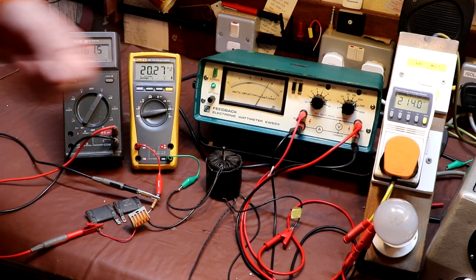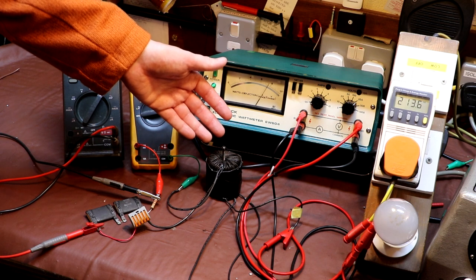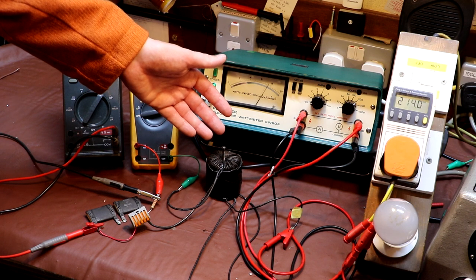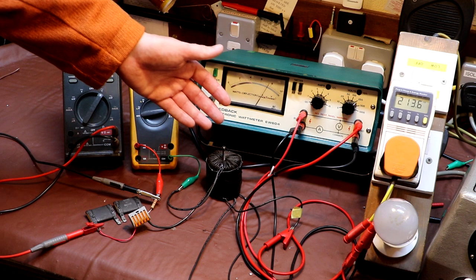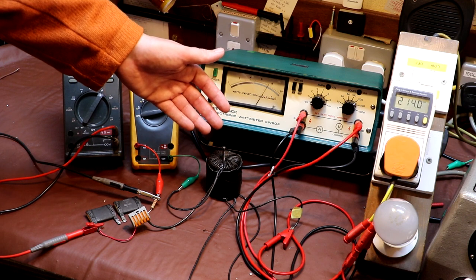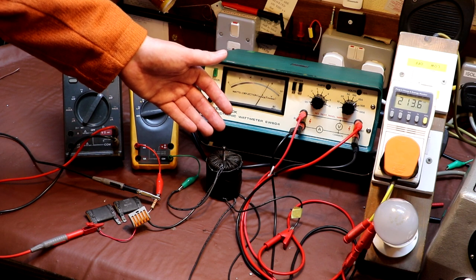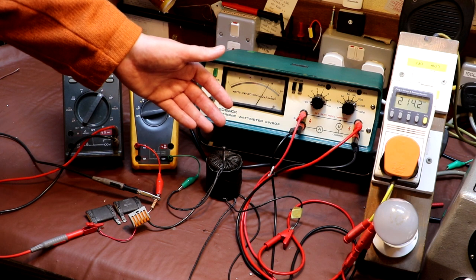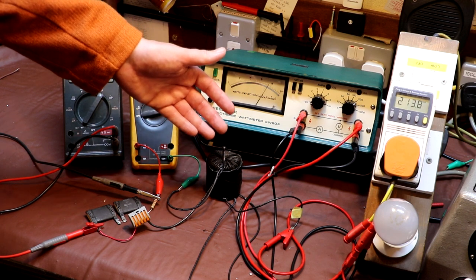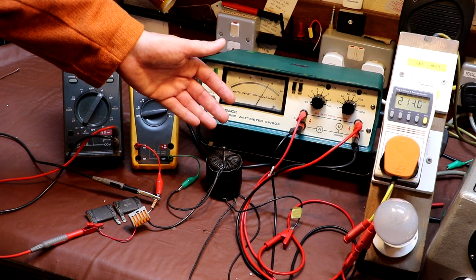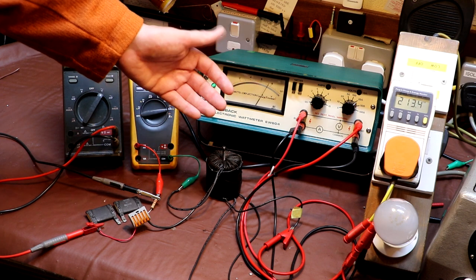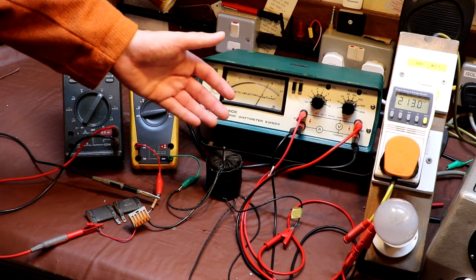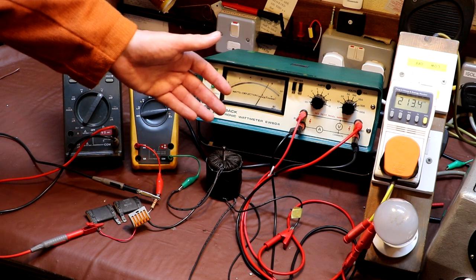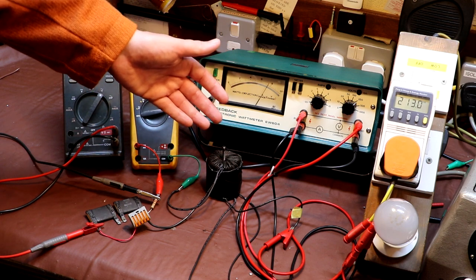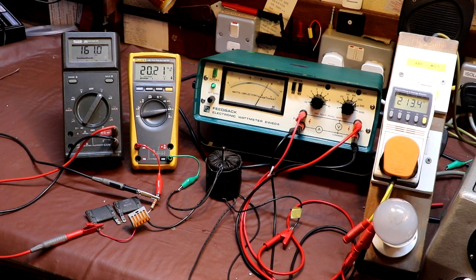So we've got 4.2 watts of losses at the moment, but we don't know how much of that 4.2 is due to iron losses and how much is due to copper losses. The actual iron and copper losses will add together to make the total value of 4.2. But what we can do is rearrange this test setup to try and measure the iron losses and the copper losses. So I'm going to have a go at doing that next.